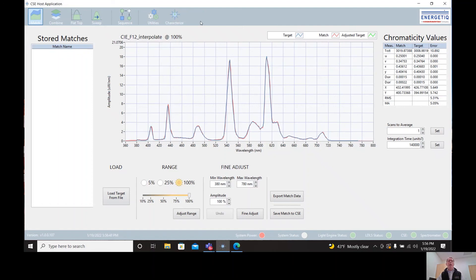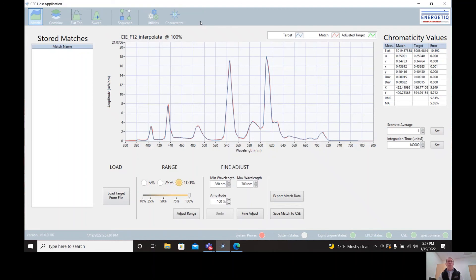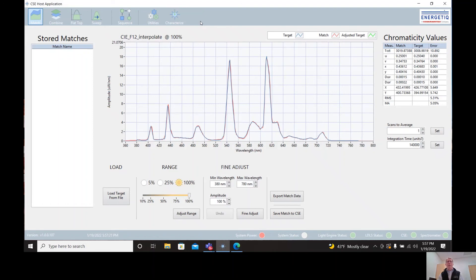And the last part I'll tell you about is the characterize function. And this is an automated procedure that's typically performed when the system is first installed or after a service procedure or after it's been transported over a significant distance. This just allows it to characterize its performance again to maintain the same performance on the first day that you use the system any day in the future. So this allows us to have a system that's very repeatable day to day. And also you can have multiple CSE systems that are going to act in just the same way in a very repeatable manner day in day out.